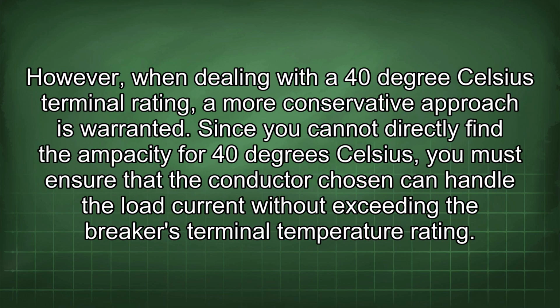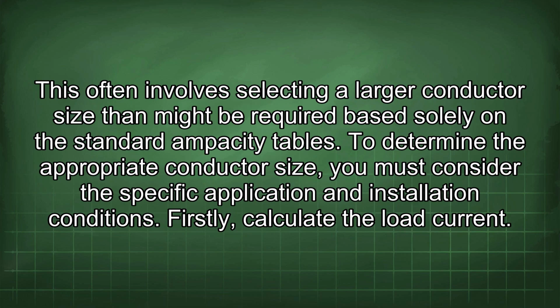However, when dealing with the 40 degrees Celsius terminal rating, a more conservative approach is warranted. Since you cannot directly find the ampacity for 40 degrees Celsius, you must ensure that the conductor chosen can handle the load current without exceeding the breaker's terminal temperature rating. This often involves selecting a larger conductor size than might be required based solely on the standard ampacity tables.